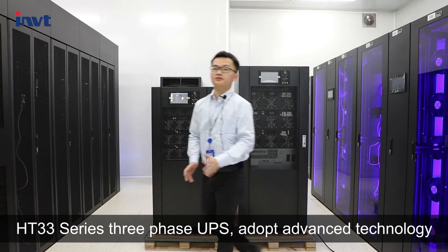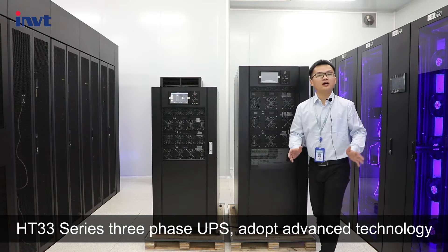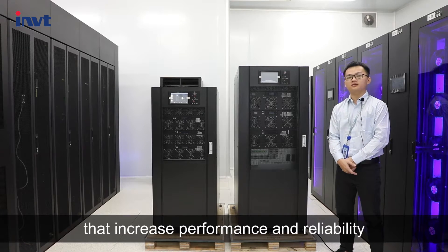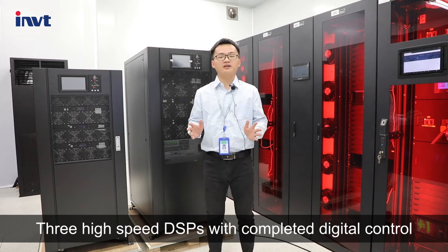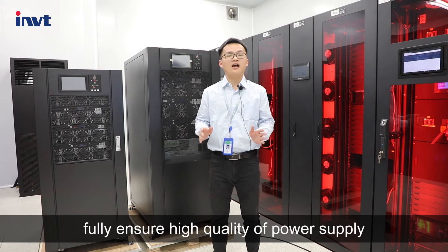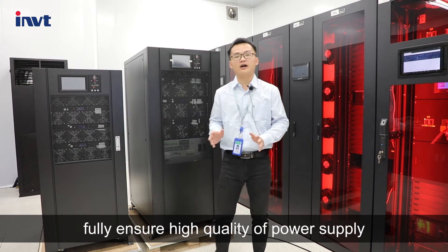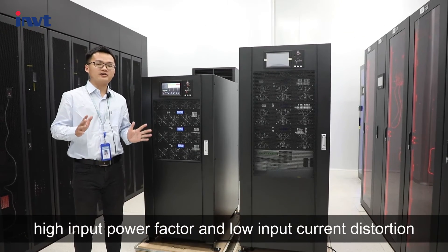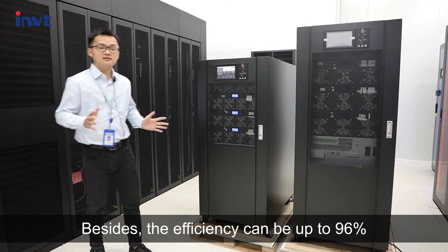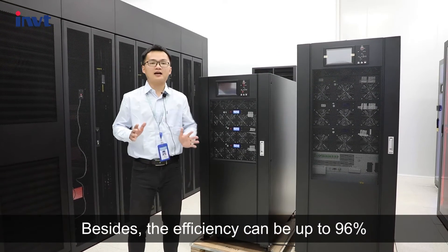The HT33 Series 3-Phase UPS adopts advanced technology that increases performance and reliability, featuring high-speed DSP with complete digital control, fully ensuring high quality of power supply. It offers high input power factor and low input current distortion, and the efficiency can be up to 96%.